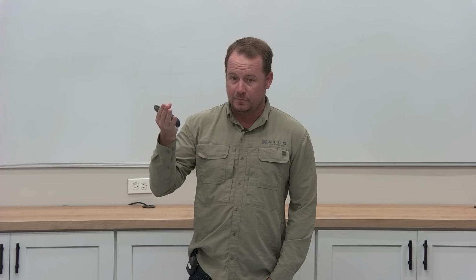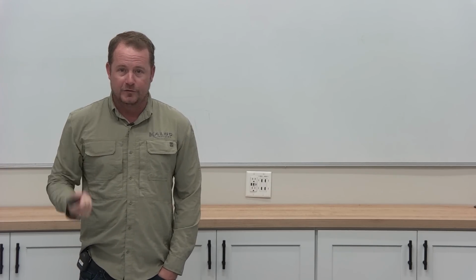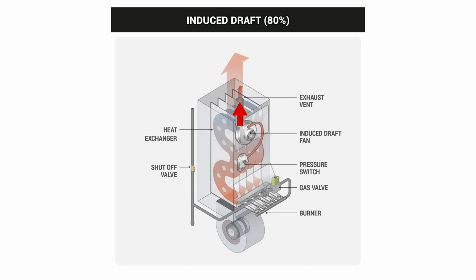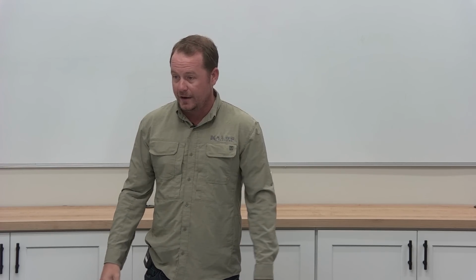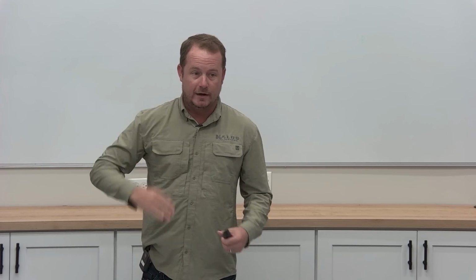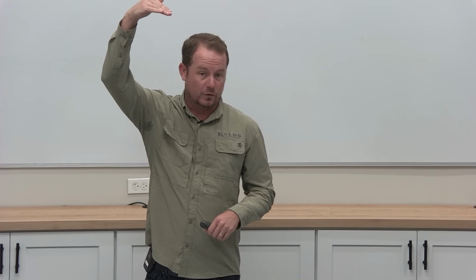Do you think it's positive pressure or negative pressure? Positive. You would imagine it would be positive. So we all imagine that that inducer fan is blowing the flue gases out of the flue pipe, right? It's actually not. It's just providing air for combustion. So it's bringing air in, but once that flame gets started, you actually have negative pressure at the outlet of the furnace. And the reason is because you're basically creating this vacuum cleaner, because what does hot air do? Hot air rises. Hot air is buoyant. It floats in colder air, right?